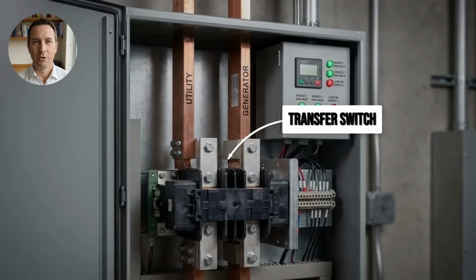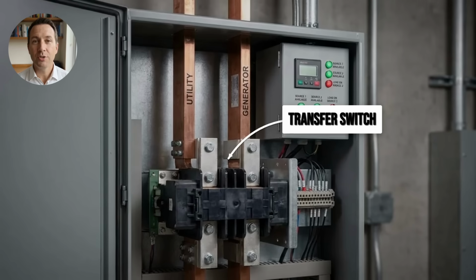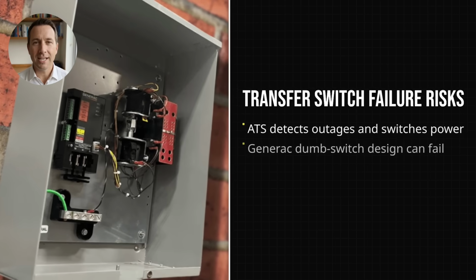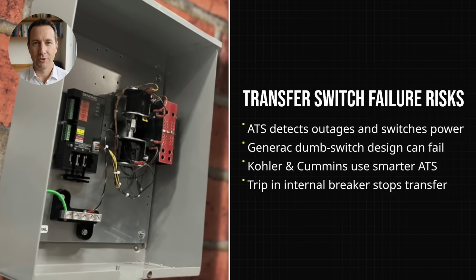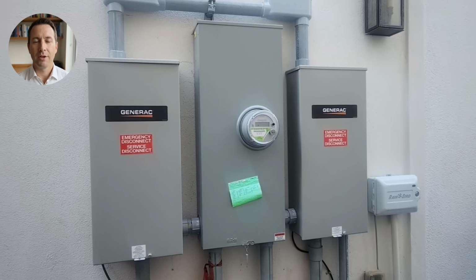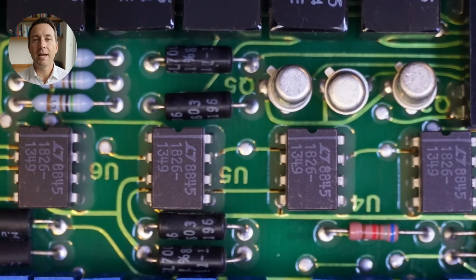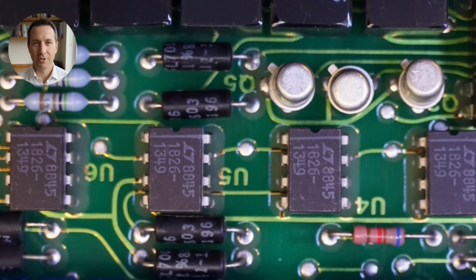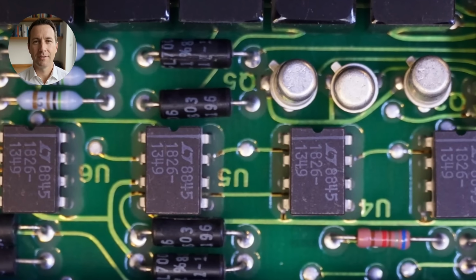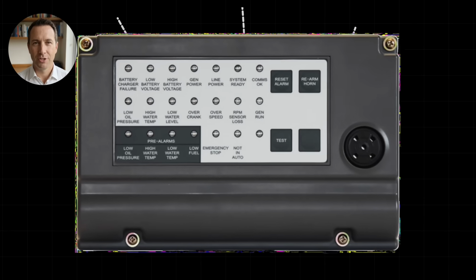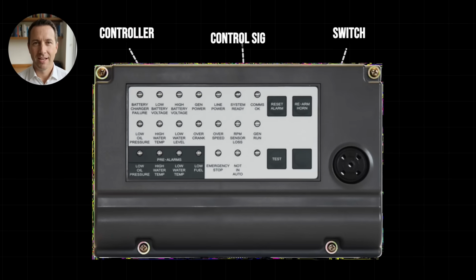Here's where it gets interesting. The component most likely to fail during an actual storm isn't the engine or the control board, it's the automatic transfer switch, the part that detects the power outage and switches your house from utility power to generator power. Generac uses what electricians call a dumb switch design, where the intelligence lives in the generator's controller, not the switch itself. So if the generator controller fails, the transfer switch can't operate even if the switch is perfectly fine.